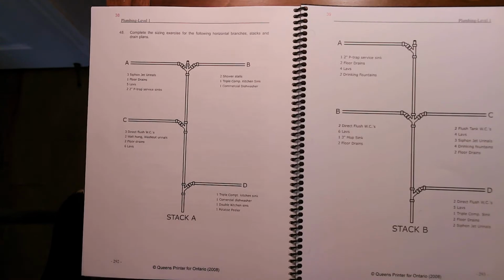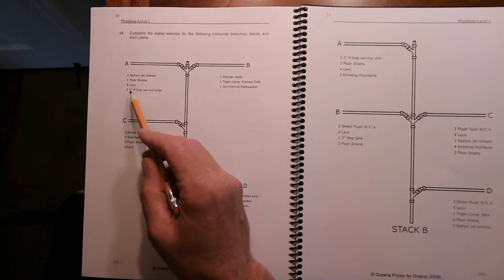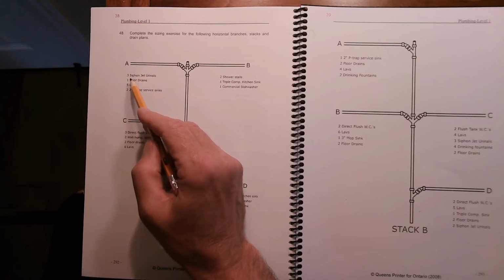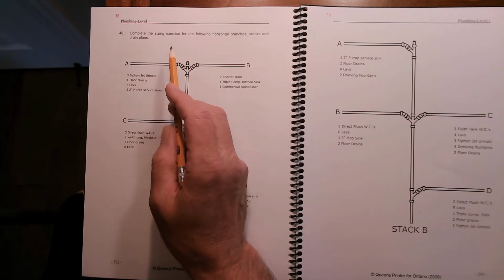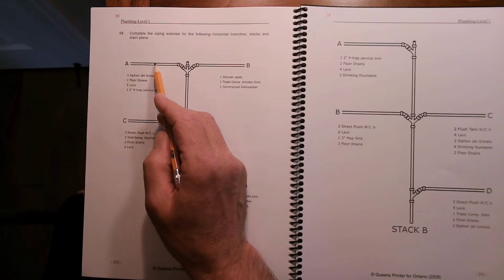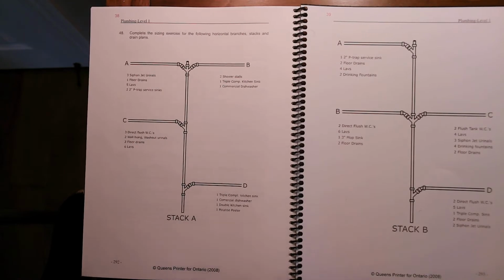Also, we're going to talk about default minimum size. So this is step 1 for sizing a pipe, is to figure out what the largest fixture on this branch is. So if the largest fixture is 4-inch, then this can't be smaller than 4-inch. That would be the size you take to certain sizing tables later on in the program, where you figure out, okay, is 4-inch large enough to handle that number of fixture units? And remember, fixture units is the approximate amount of water, or wastewater, you're going to get out of a fixture. Anyway, so let's give this a shot.